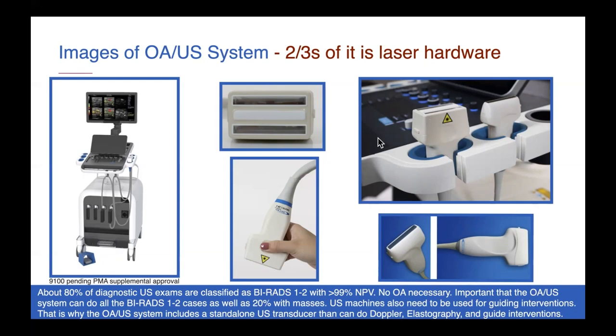And importantly, we have a standard ultrasound probe as well as the duplex probe, for a couple of reasons. First, ergonomically, this stiffer, thicker cord could be more fatiguing during the day. But more importantly, the approval for OA is for better characterization or classification of solid, or complex cystic and solid, masses between BI-RADS 3 and 5. The truth is, depending on your case mix, somewhere between 70 and 90% of all your ultrasounds are going to be BI-RADS 1 and 2. In those cases, there isn't much point doing OA.